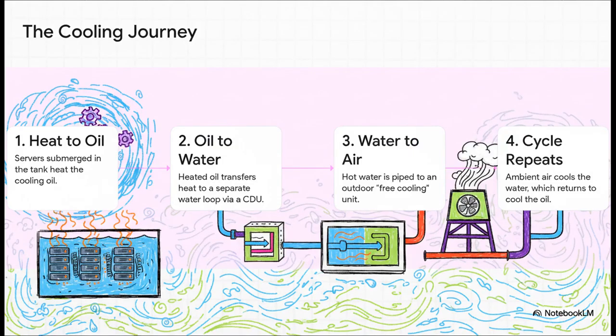It's basically a four-step journey for the heat. Step 1: the servers sit in this oil, and the oil sucks the heat right out of them. Step 2: that now hot oil gets pumped to a heat exchanger—they call it a CDU—where it transfers its heat to water. Step 3: that hot water is piped outside to a free cooling unit. Step 4: that outdoor unit uses the regular outside air to cool the water down, and that cool water cycles right back inside to cool the oil again. It's a brilliant, low-energy way to get heat from the chip all the way outside.